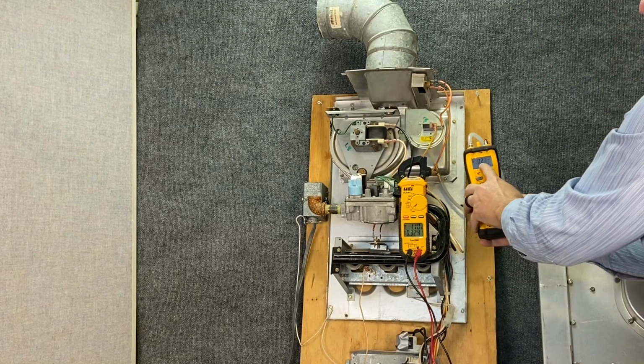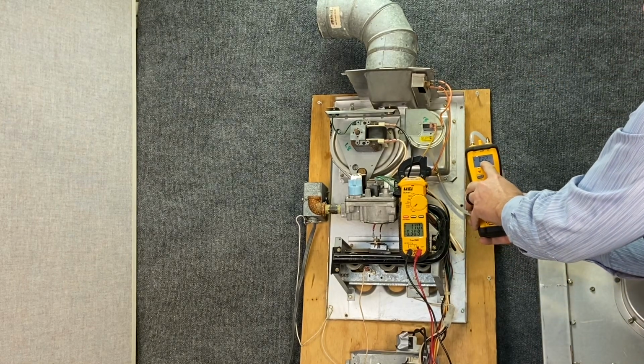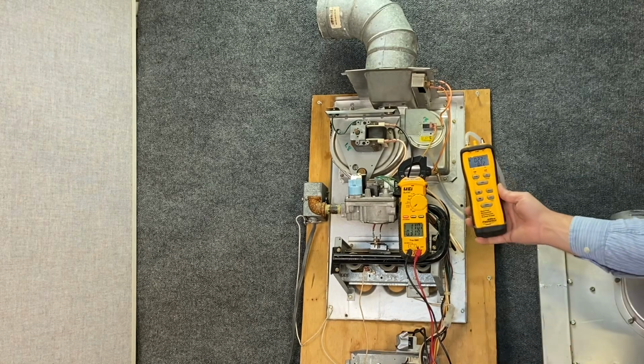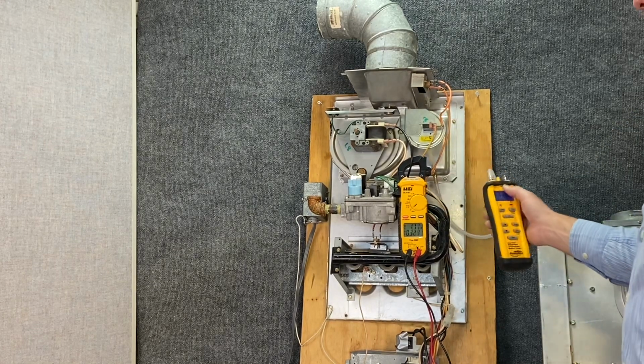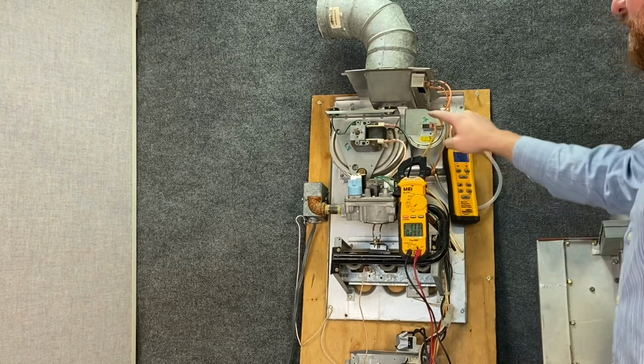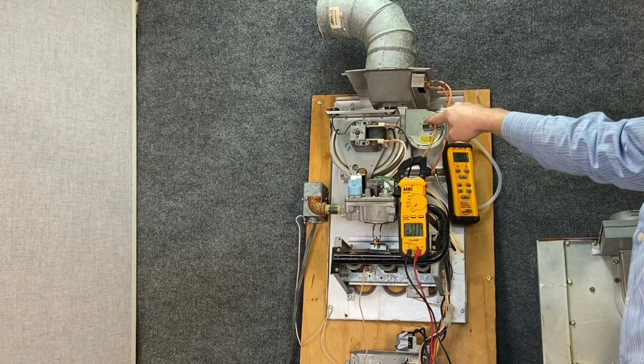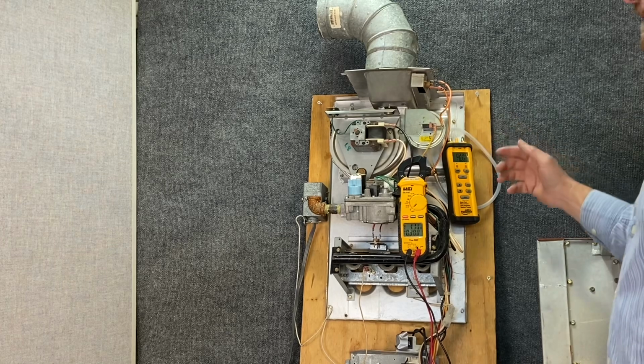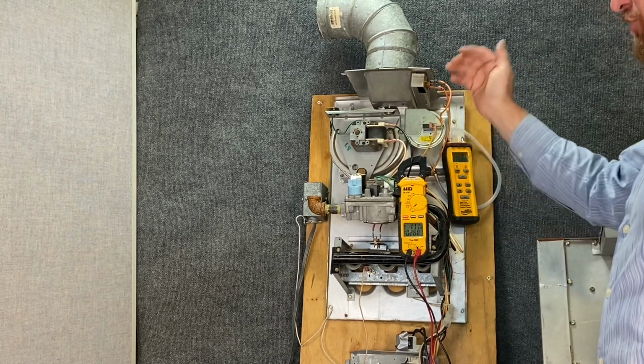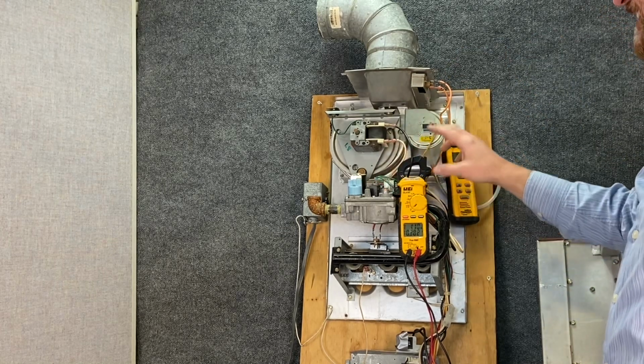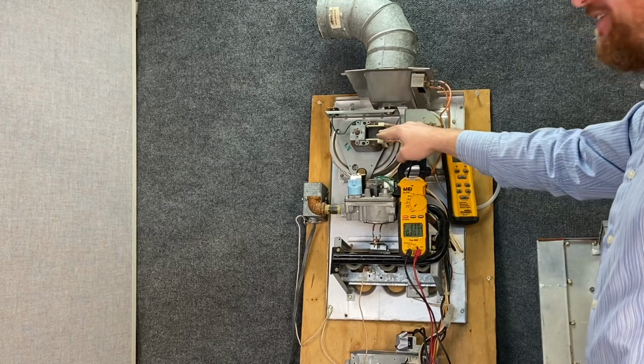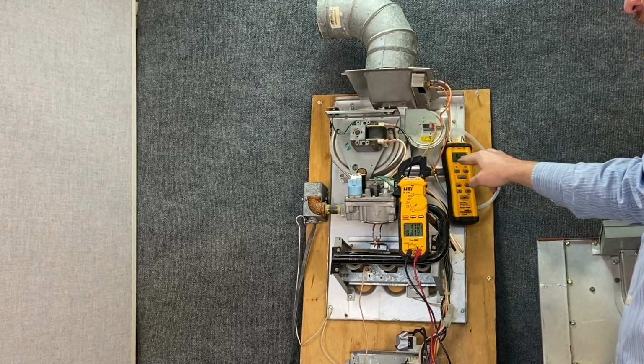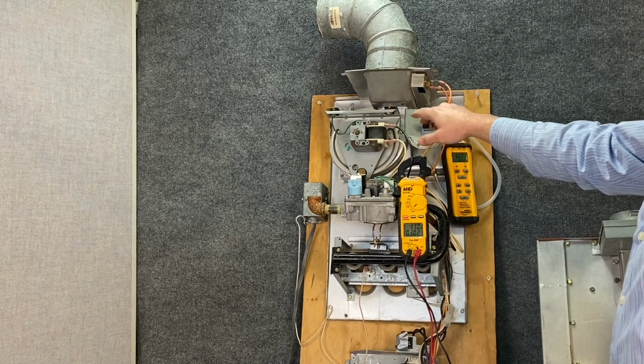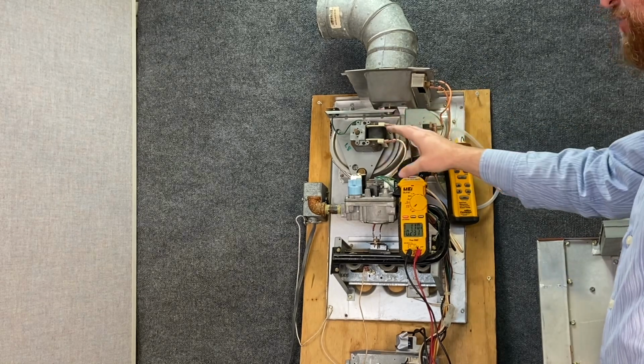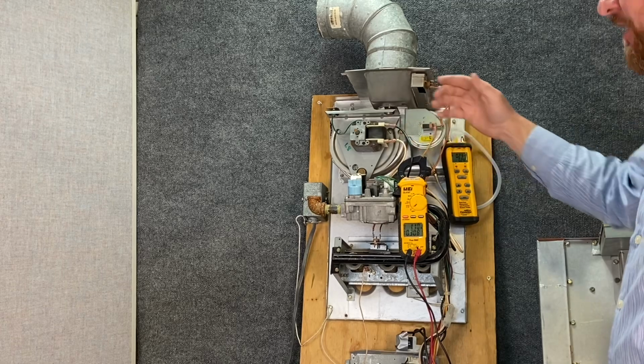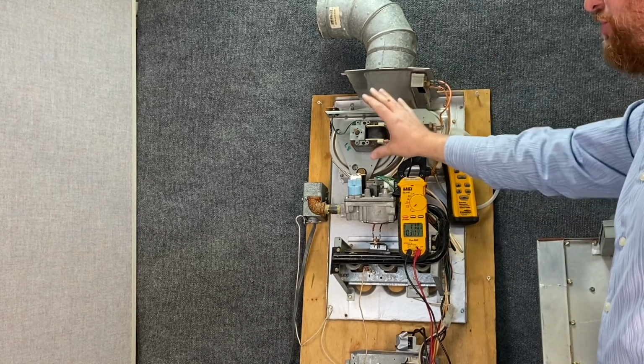Now my manometer is reading the inches of water column. So I'm pulling 0.22 inches of water column for this furnace. I should be pulling 0.3 inches of water column for my pressure switch to close. So people say all the time, is it my pressure switch or is it my motor? Well, in this case, I can tell you for sure that the motor is not pulling enough of a vacuum to my pressure switch. So my switch shouldn't be closing. I have an issue with my motor, which could be the motor, it could be the wheel, could be the heat exchanger, but my issue is on this side.